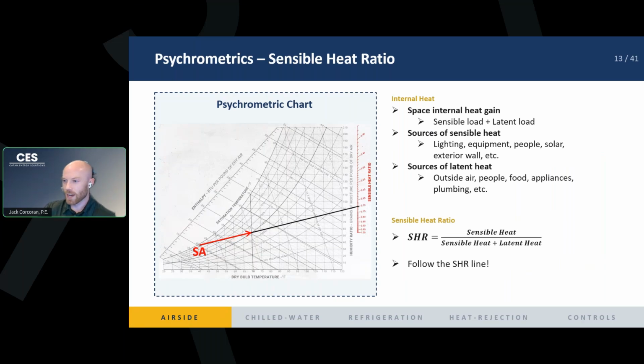But sensible heat ratio is important for determining what our supply air temperature needs to be, right? What our temperature and our humidity need to be.